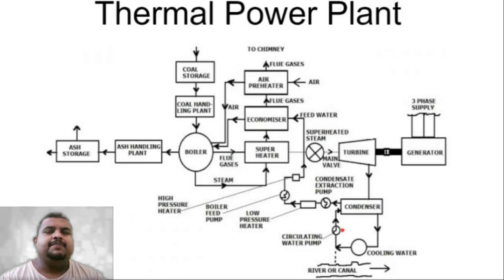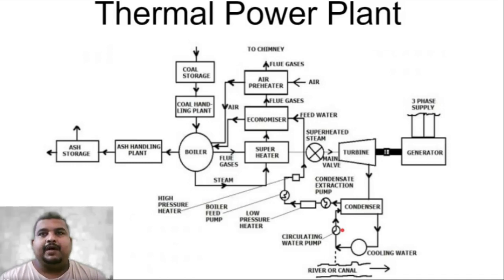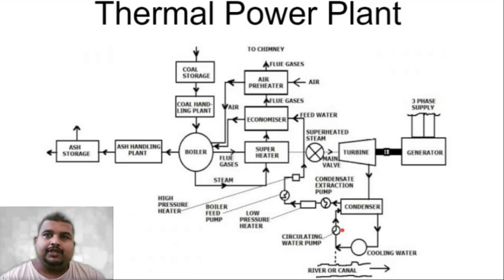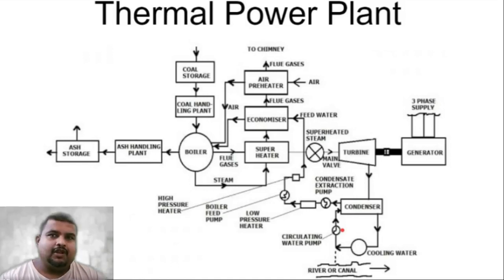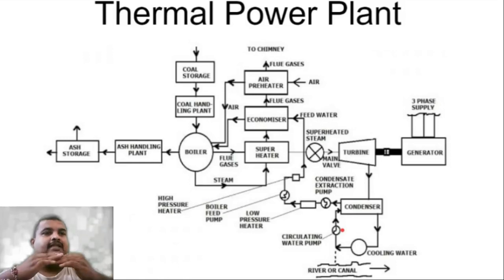The boiler feed pump is a pump in the entire power system because of which your entire cycle runs properly. The BFP provides water to the boiler at a pressure higher than the boiler's own pressure. The water coming from the CEP is heated here in stages: LP heater 1, LP heater 2, LP heater 3 — and after that it goes towards the boiler feed pump. Before the BFP there is a device called a deaerator, which separates any air accumulated in the condensate from the water.